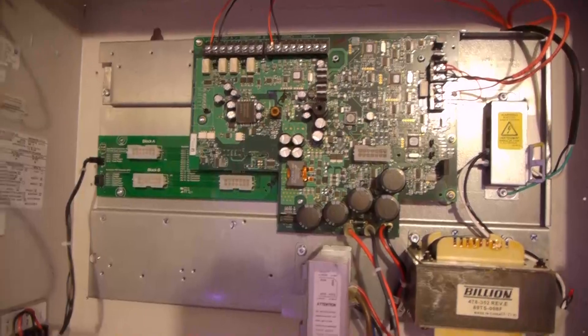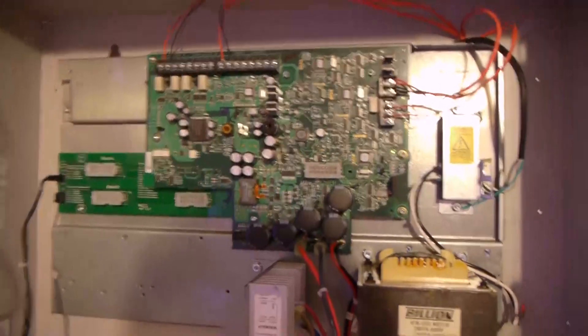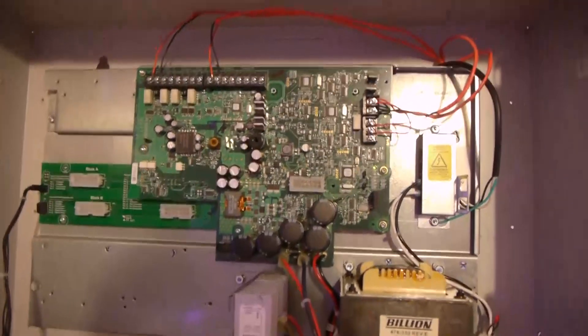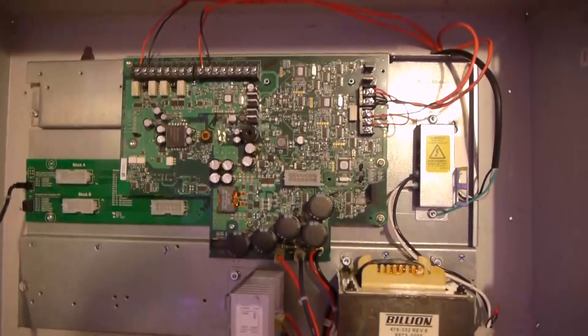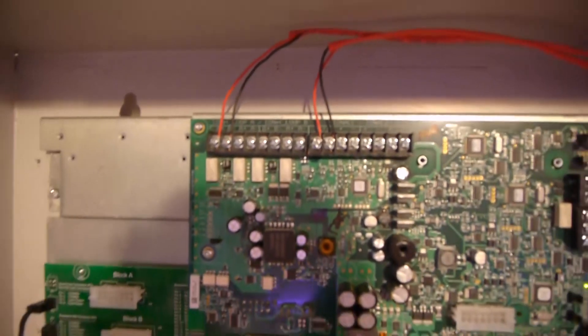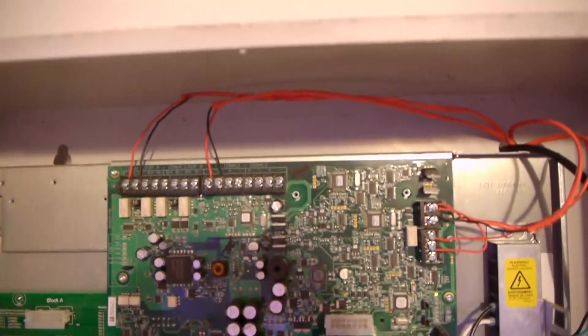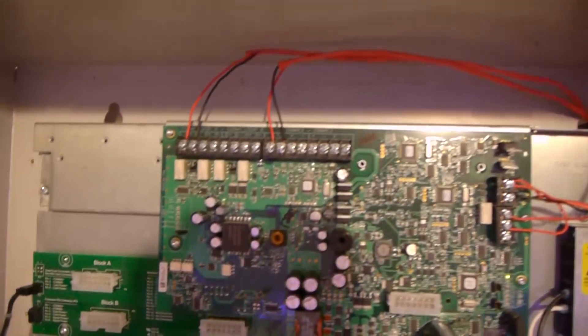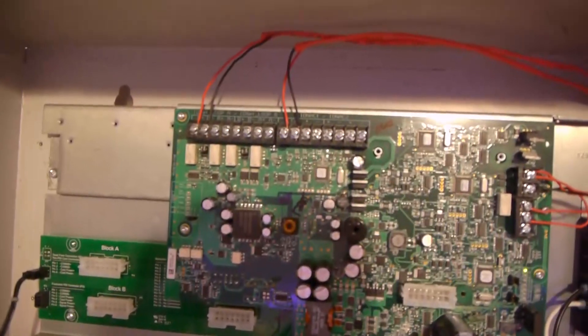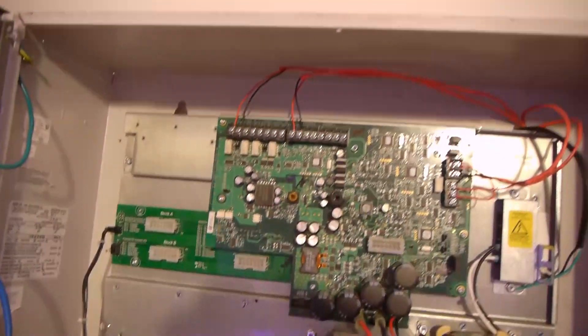There's the transformer for power. Now here is the main power supply. Now this is IDNAC addressable, so this panel does not have any NAC circuits, it has an IDNET loop, which most of you probably know is for addressable smoke detectors, basically an SLC. So that's the SLC for this panel, and right next to it we have IDNAC, which is for notification.